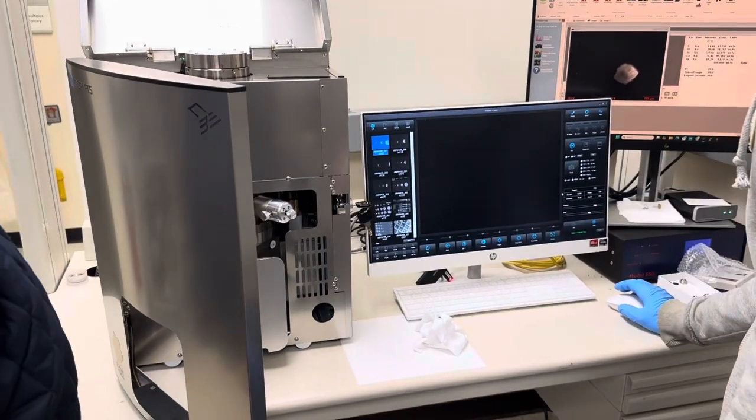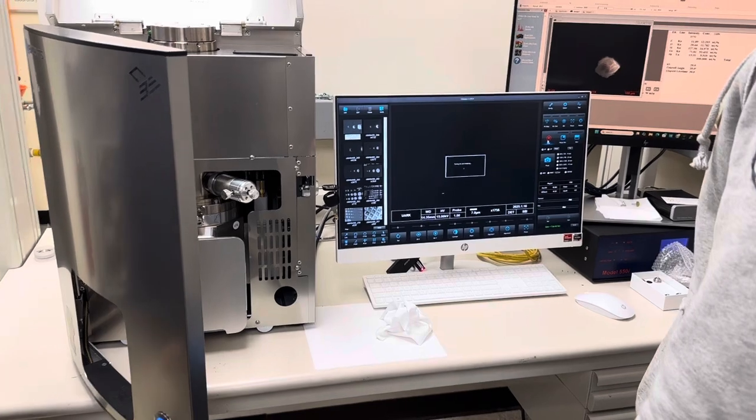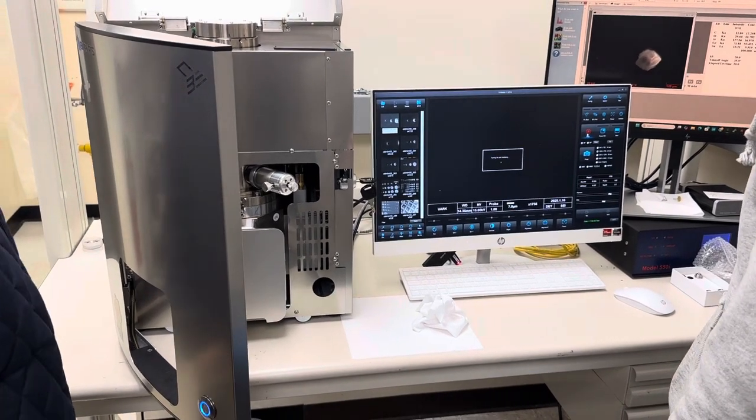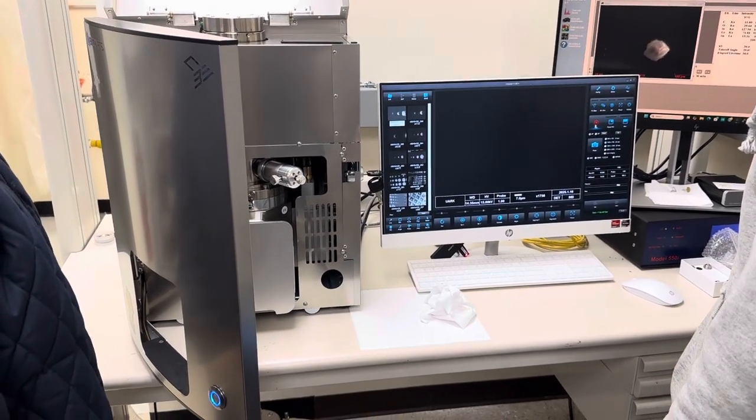See, hey, what's going to happen, right? So we hit run. And then we just kind of wait to bring the beam up. Our worst case scenario would be that we don't see anything, right? Just like right now, that's our worst case scenario. We don't see anything. But do we have gun current? That's really important.